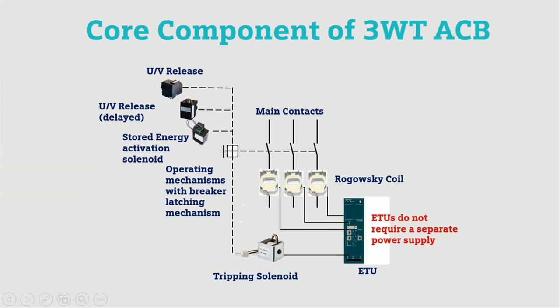There are fixed contacts and moving contacts. In case of a fault condition, the electronic trip unit will give a signal to the tripping solenoid and the mechanism will trip, causing the moving contact to break from the fixed contact.